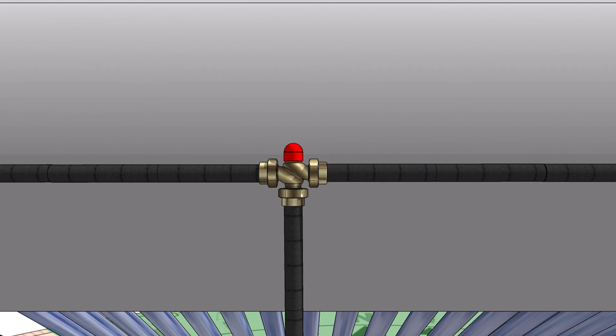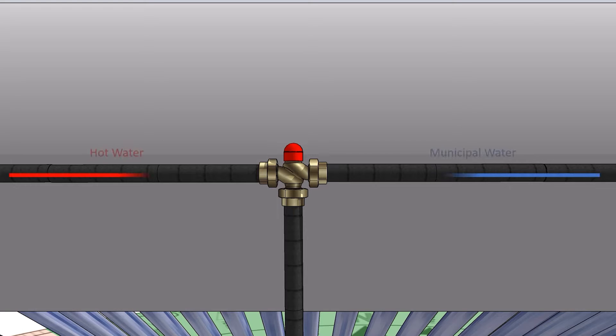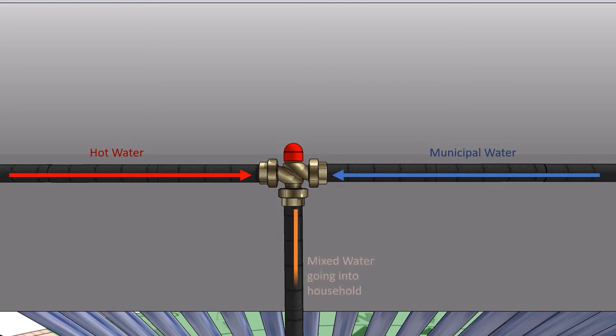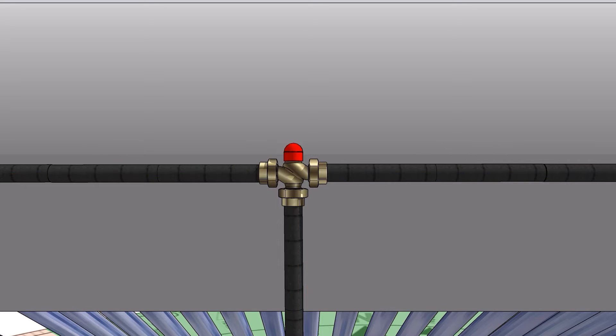Tempering valve. Stipulated in SANS regulations that in order for a plumbing certificate of compliance, a COC to be issued, a mixing or tempering valve must be installed before the hot water enters into the household.